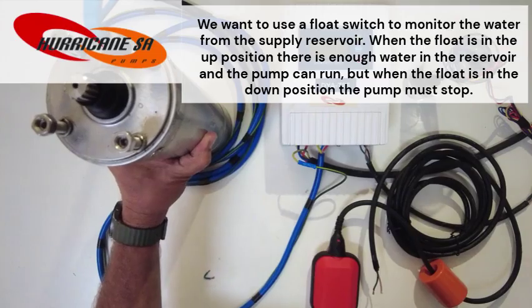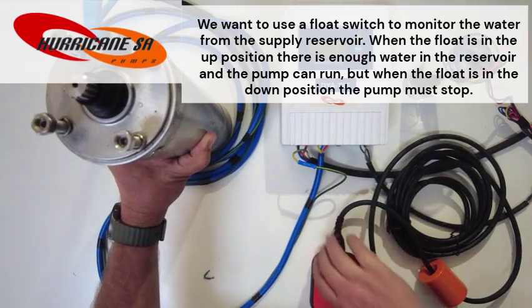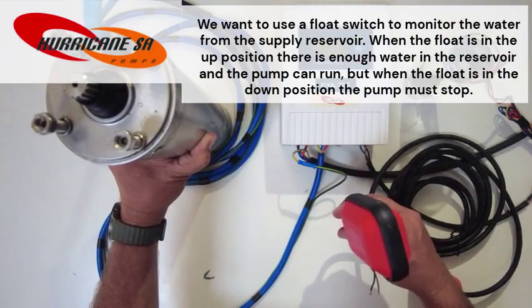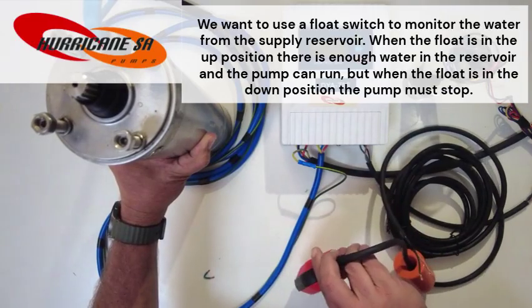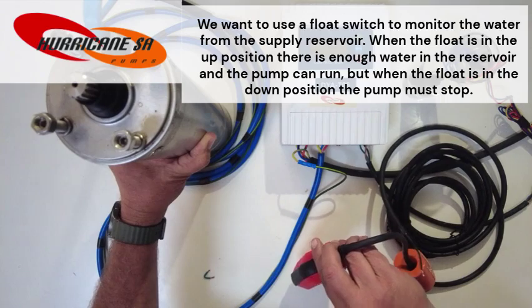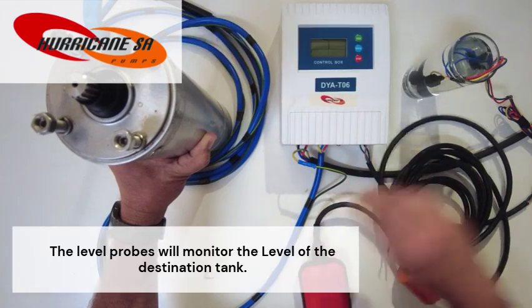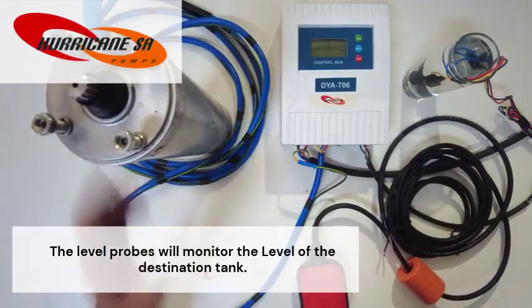We want to use a float switch to monitor the water from the supply reservoir. When the float is in the up position, there is enough water in the reservoir and the pump can run. But when the float is in the down position, the pump must stop. The level probes will monitor the level of the destination tank.